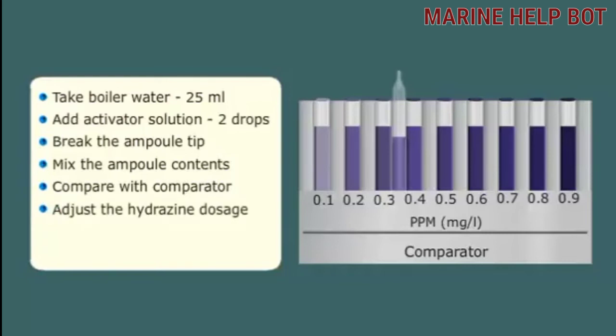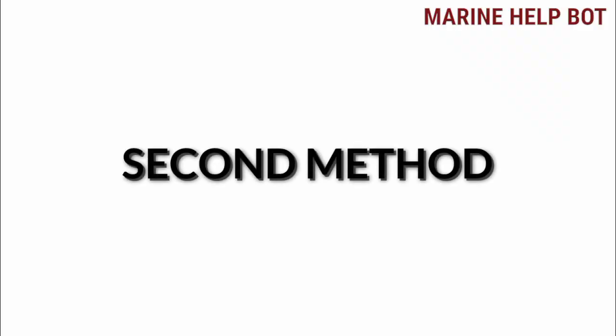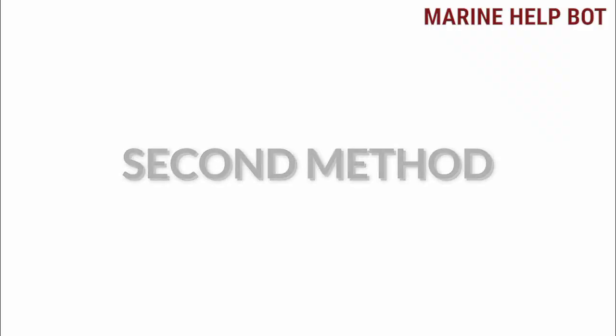Adjust hydrazine dosage to the boiler water so that hydrazine reserve is maintained between 0.1 to 1 parts per million. There is one more method by which we can perform this test.